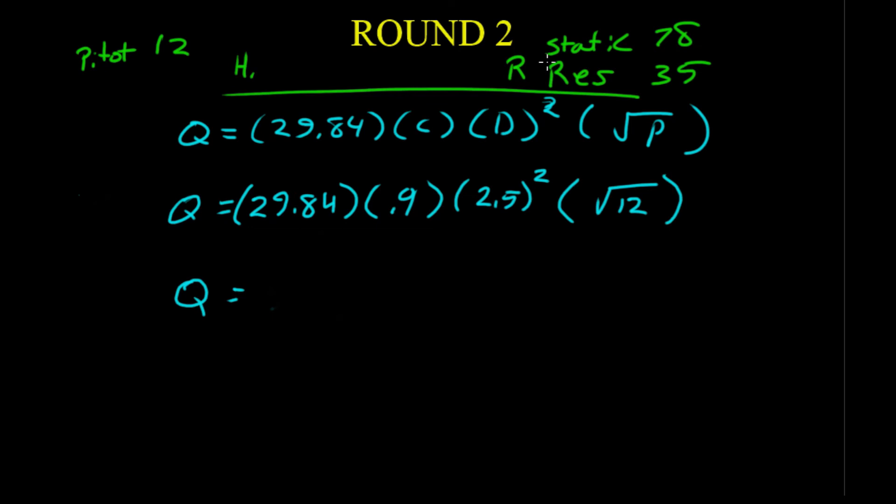New hydrant flow test. We have a pitot pressure of 12 on this fire hydrant. We have a static of 78 and we have a residual of 35. So, 29.84 times 0.9 times 2.5 squared times the square root of 12.